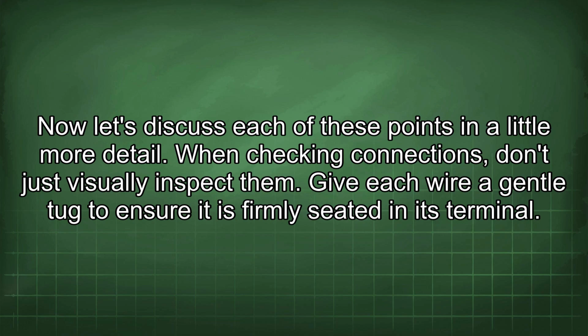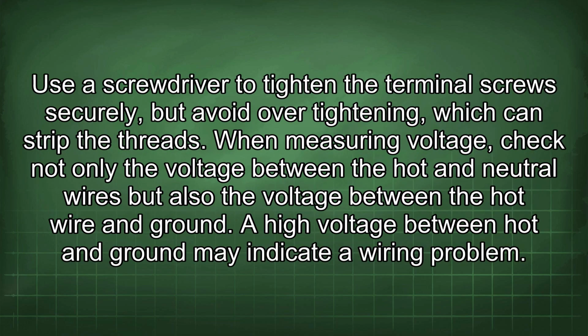When checking connections, don't just visually inspect them. Give each wire a gentle tug to ensure it is firmly seated in its terminal. Use a screwdriver to tighten the terminal screws securely, but avoid over-tightening, which can strip the threads. When measuring voltage, check not only the voltage between the hot and neutral wires, but also the voltage between the hot wire and ground. A high voltage between hot and ground may indicate a wiring problem.